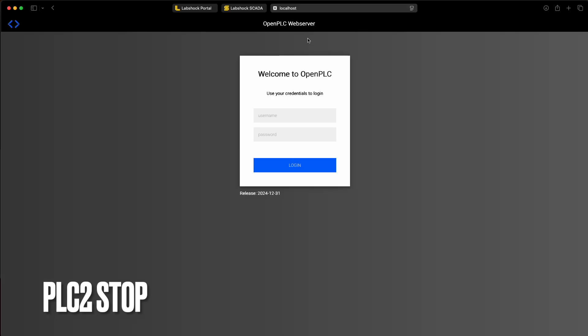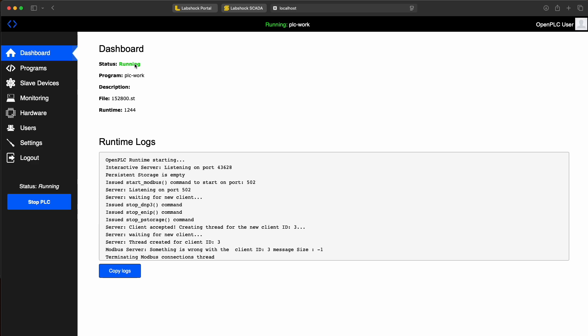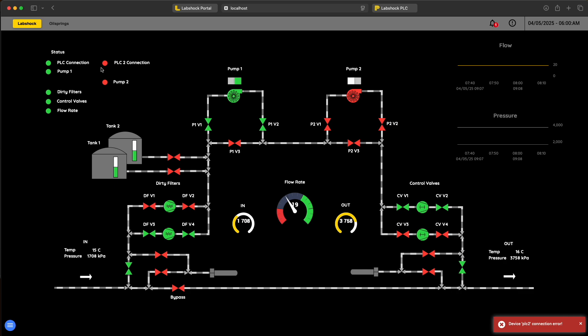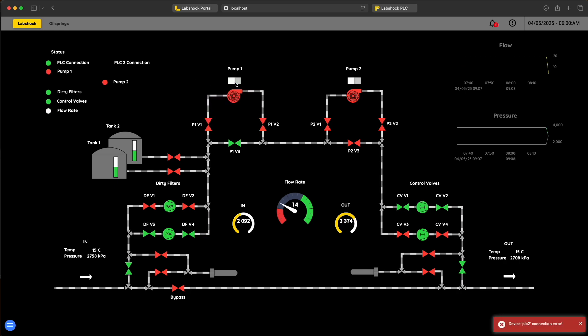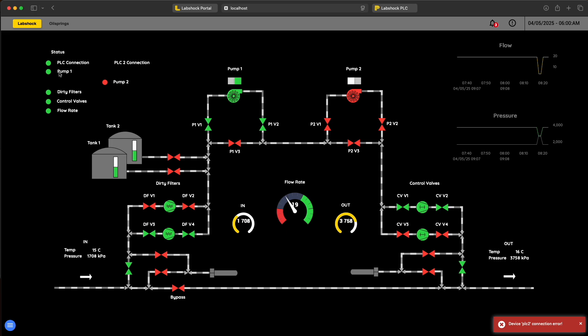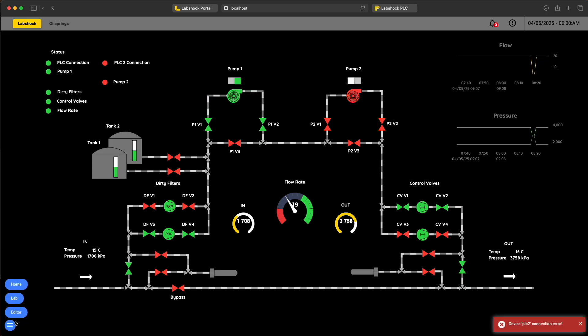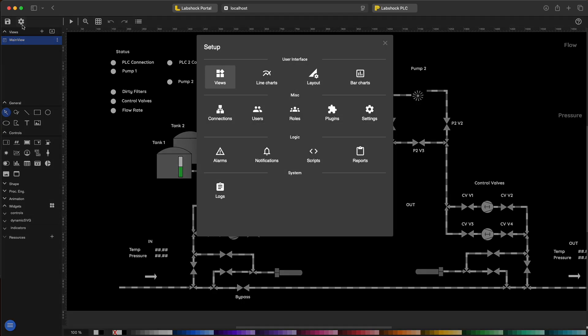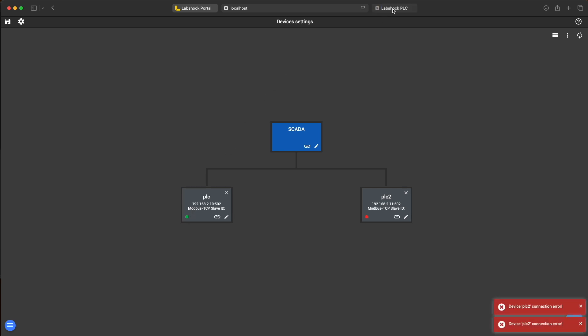Now let's stop the PLC2 to see how our pump will react to it. We login to the PLC2 and stopping it. Here on SCADA first we see that PLC2 connection is red and pump 2 is not working, it's also red. But pump 1 is working and connection with PLC1 is ok. Let's go into the settings, into the connection tab. And we can see also yellow and errors are bumping and showing us that something wrong with PLC2.